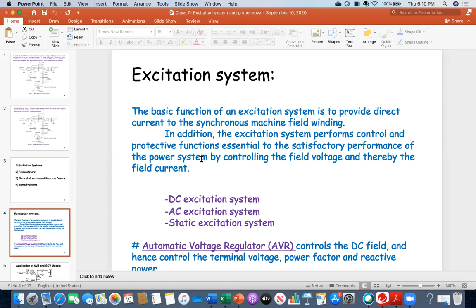So now let's go to the excitation system. As I already mentioned, excitation system refers to magnetization. In case of synchronous machine, it is magnetization to the physical poles. In case of induction machine, that excitation comes from the grid in terms of reactive power. So here we are focusing on the synchronous machine, keep in mind this discussion is mainly dedicated to the synchronous machine.